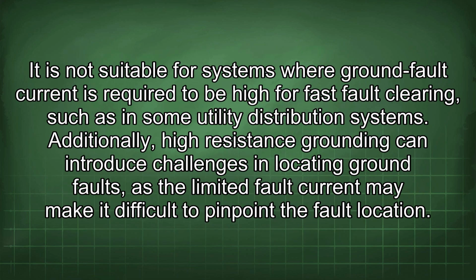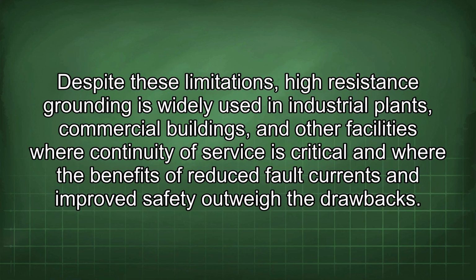It is not suitable for systems where ground fault current is required to be high for fast fault clearing, such as in some utility distribution systems. Additionally, high-resistance grounding can introduce challenges in locating ground faults, as the limited fault current may make it difficult to pinpoint the fault location. Despite these limitations, high-resistance grounding is widely used in industrial plants, commercial buildings, and other facilities where continuity of service is critical and where the benefits of reduced fault currents and improved safety outweigh the drawbacks.